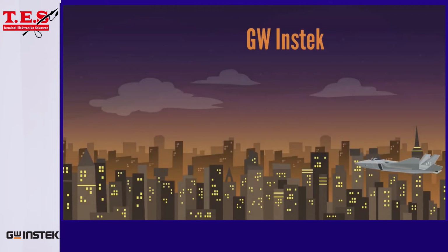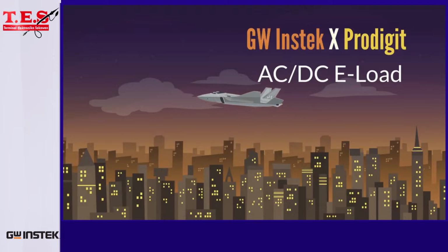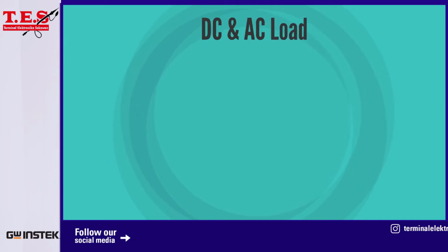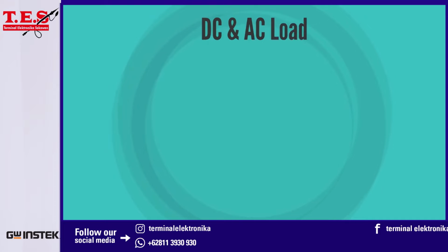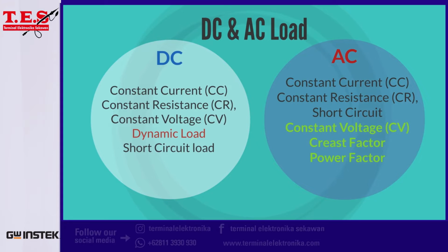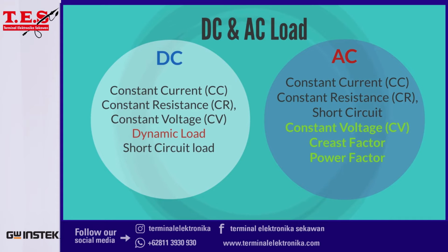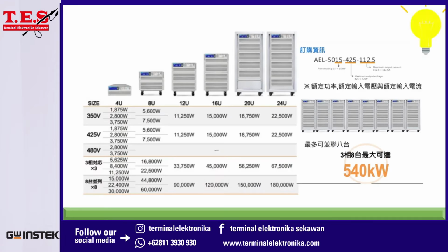Loads can be resistive, inductive, capacitive, or mixed type. Real load behavior is typically more complex. They can be dynamic and various. GW-Instek DC electronic load can emulate such as constant current, CC, constant resistance, CR, constant voltage, CV, dynamic and short circuit load. AC electronic load can emulate more like crest factor, CF, power factor, PF and short circuit load.